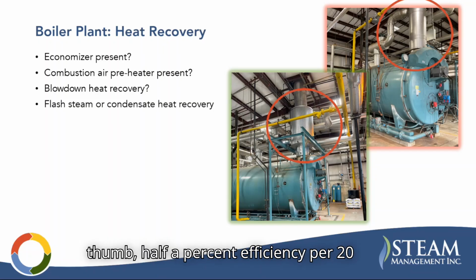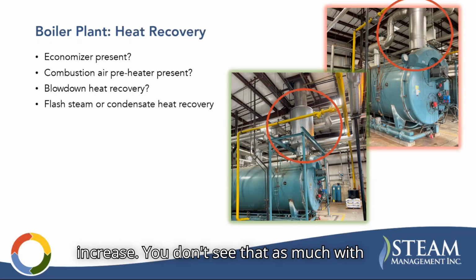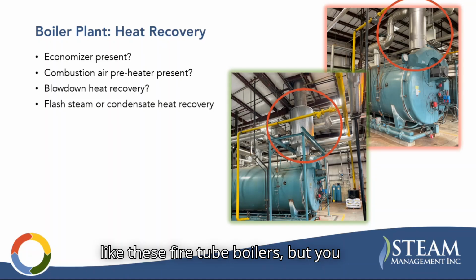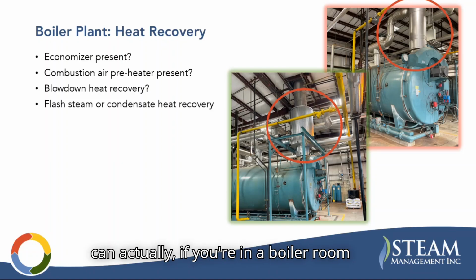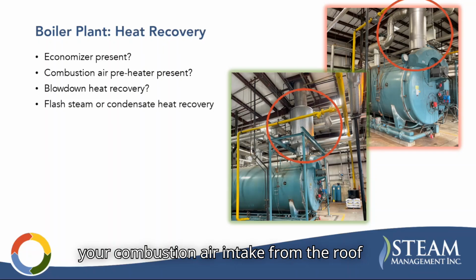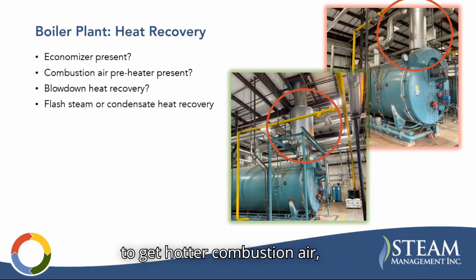Combustion air preheater rule of thumb: 0.5% efficiency per 20-degree combustion air temperature increase. You don't see that as much with these fire tube boilers, but when you get into larger boilers, preheating the combustion air can make a big difference. One thing you will see with these types of boilers: if you're in a boiler room that has a high ceiling and it's pretty hot in there, you can pull your combustion air intake from near the ceiling, where it's stratified up there, and get hotter combustion air and some efficiency gain.